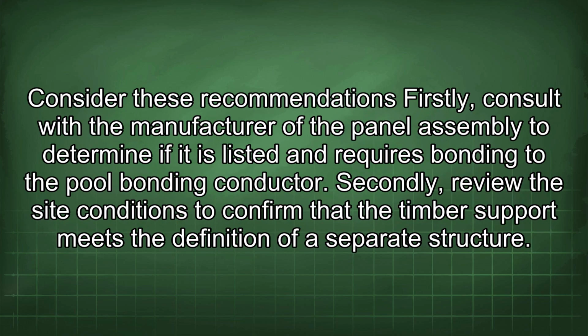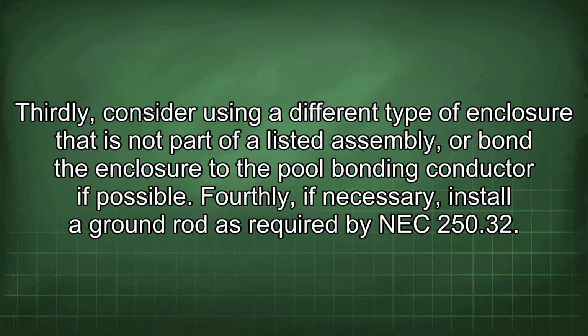Firstly, consult with the manufacturer of the panel assembly to determine if it is listed and requires bonding to the pool bonding conductor. Secondly, review the site conditions to confirm that the timber support meets the definition of a separate structure. Thirdly, consider using a different type of enclosure that is not part of a listed assembly, or bond the enclosure to the pool bonding conductor if possible. Fourthly, if necessary, install a ground rod as required by NEC 250.32.